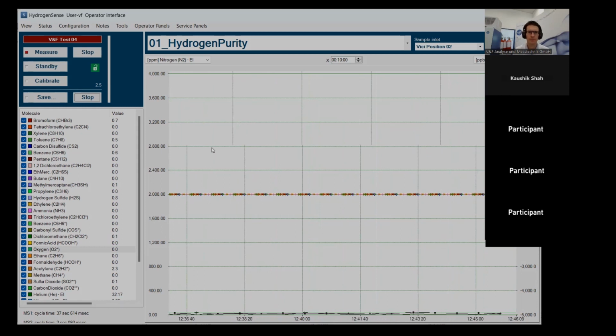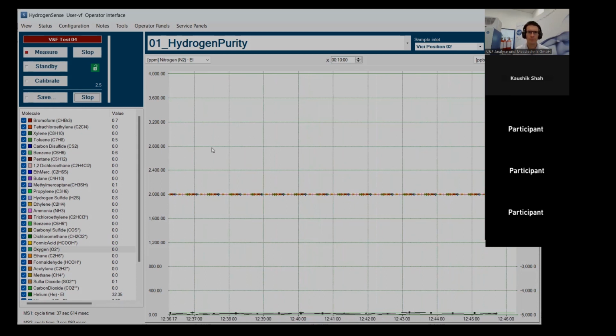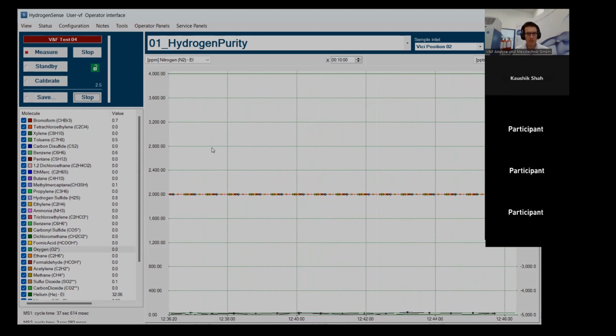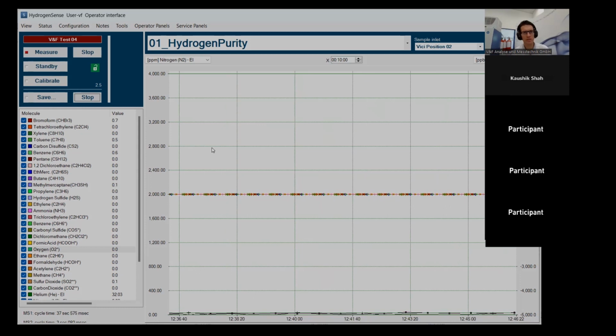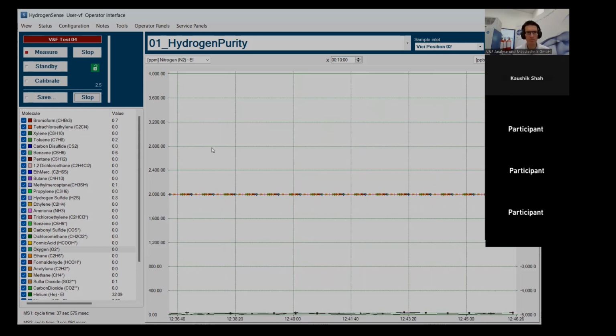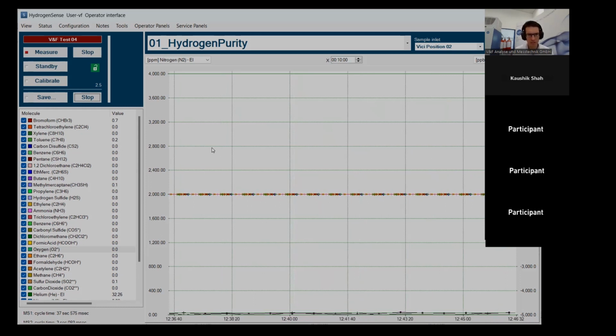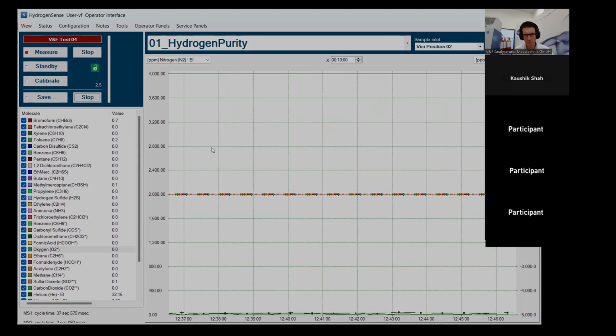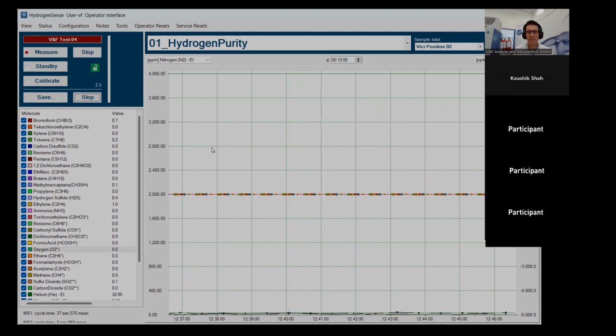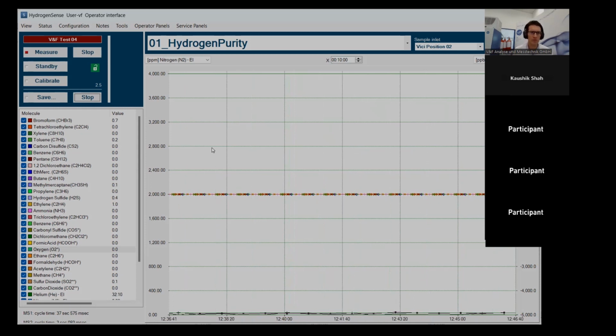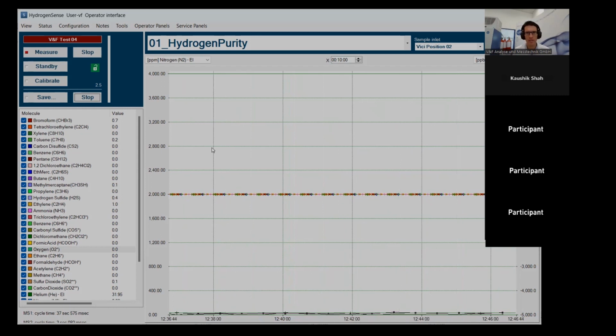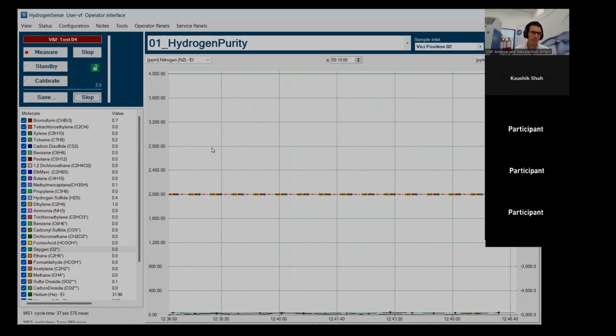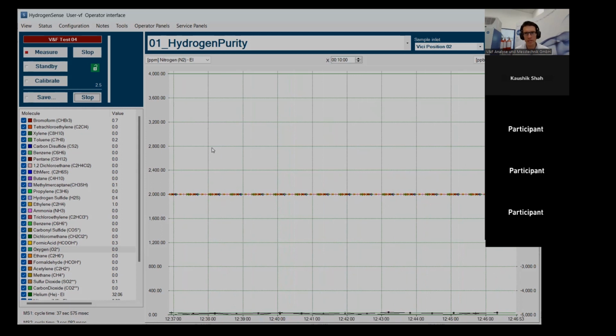Okay. My next question is, what is your recommendation about the frequency of calibrations? Yeah, this is a very good point. What my experience is that it makes sense to have a background calibration before each analysis, especially for the sulfur compounds. I mean, 1 ppb of background offset is something that can easily occur. So what we usually recommend is to have background calibration before you switch to the gas that you actually want to analyze. And for the sensitivity calibration, I would recommend doing it twice a week.